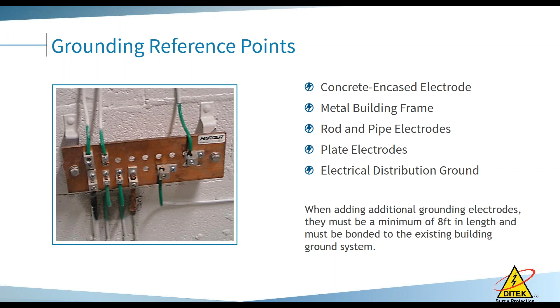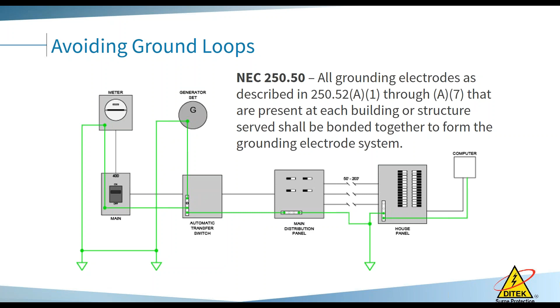Avoid grounding loops. They always have to have common bond. You always want to bond these grounds together. Otherwise, you have a difference in potential, and they're going to try and even out through the wires connecting these different panels, which a lot of times are low voltage cables, and you can have surge protection issues just because your grounds are all different.